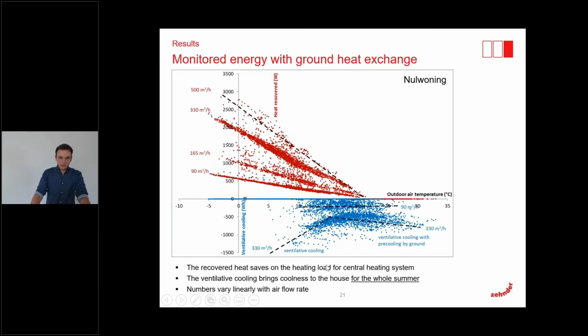This is the same graphic, but here it shows the energy savings with the ground heat exchanger. What we can see here is that in winter it's almost the same. We are a little bit more efficient, but the bigger effect is in summer, when we make use of ventilative cooling with the pre-cooling by ground. And what we can also see here is that we do not have cold recovery when we have a ground heat exchanger, because we use the ground heat exchanger and we avoid the cold recovery. So we avoid the heat exchanger.